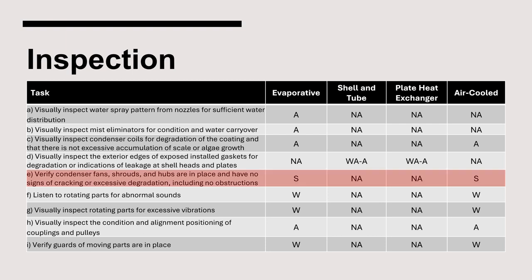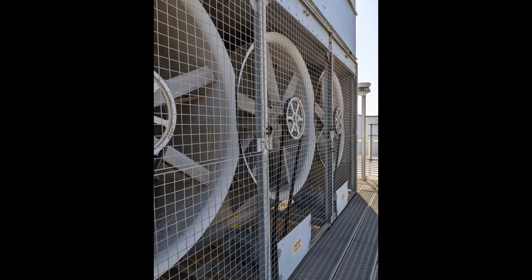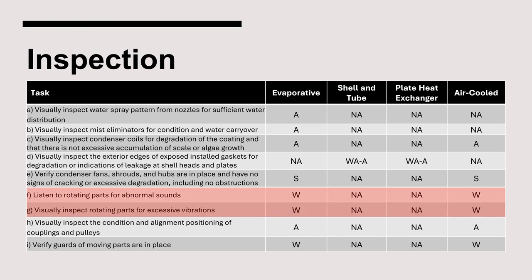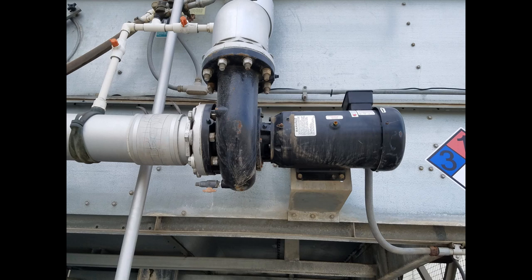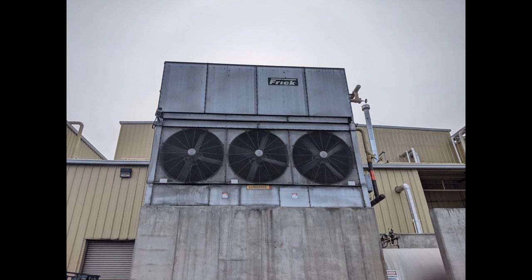Next, inspection items are to verify the condenser fans, shrouds, and hubs are in place and in good condition. The couplings and pulleys should also be inspected to ensure they are in good condition and proper alignment. Here we can see a properly guarded condenser with the fan shroud in place. On a weekly basis, listen to rotating parts for abnormal sounds and excessive vibrations. Additionally, verify guards of moving parts are in place. Each pump and fan shaft should be properly guarded. Visually inspect that supports are in place for each condenser. Condenser supports are often constructed of concrete or steel.